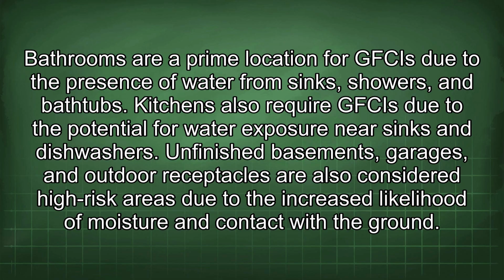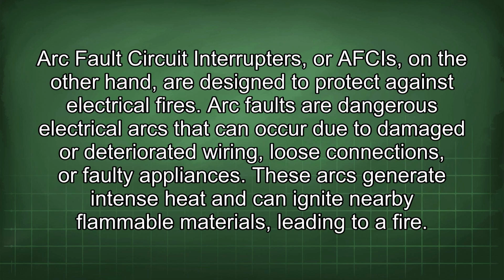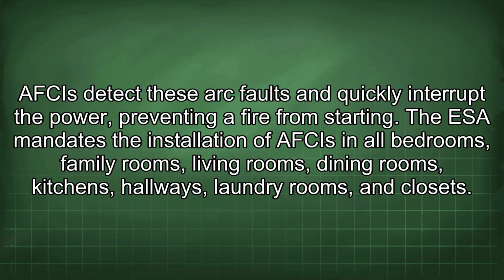with the ground. Arc fault circuit interrupters, or AFCIs, on the other hand, are designed to protect against electrical fires. Arc faults are dangerous electrical arcs that can occur due to damaged or deteriorated wiring, loose connections, or faulty appliances. These arcs generate intense heat and can ignite nearby flammable materials, leading to a fire. AFCIs detect these arc faults and quickly interrupt the power, preventing a fire from starting.